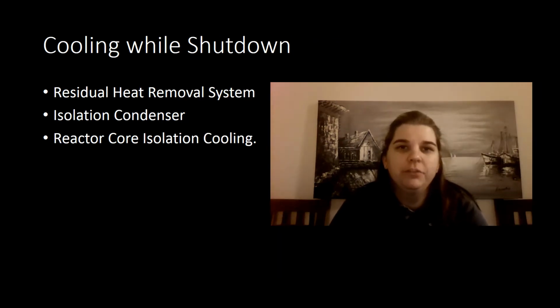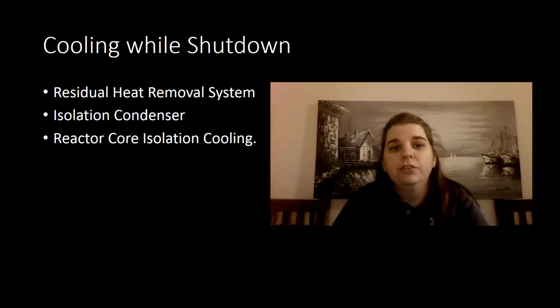There are several ways to remove heat from the reactor core while shut down. The first is the residual heat removal system. This system operates off of diesel generator power. The system uses smaller pumps to circulate water through the reactor pressure vessel, removing heat and transferring it to the residual heat removal heat exchangers. The heat is then dumped into the sea.